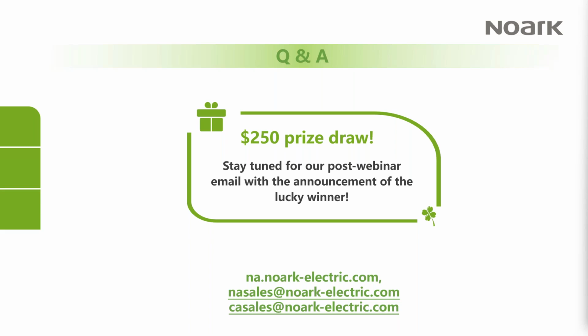Okay, and then just one other one. Is there a barrier for the service entrance enclosure, just to clarify what you were talking about previously? Yeah, so we're working on that. It's actually going to become a fairly high priority design program for us, because we were just working with UL and they informed us that early next year the UL 489 standard will include that provision. It's already in the code, so there's a little bit of risk that a local inspector will flag the lack of a barrier there. But it's our understanding that there aren't any jurisdictions enforcing that rule yet, because it's brand new in the code.